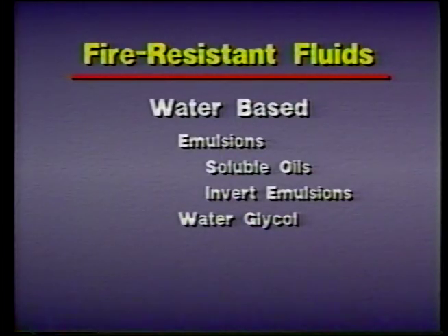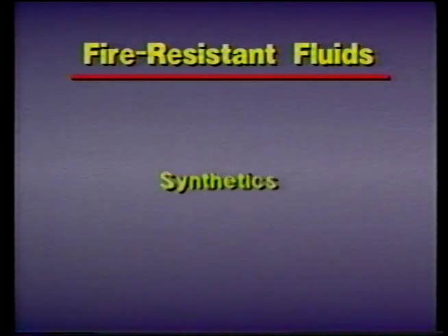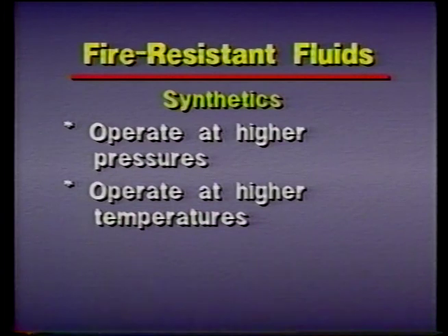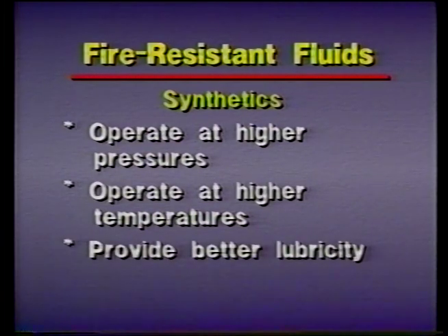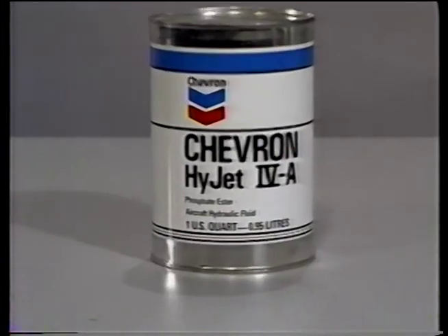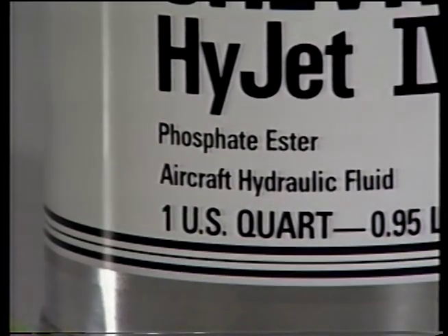The last category of fluids we need to discuss are the synthetic fluids. These man-made solutions operate at higher pressures and higher temperatures. They provide better lubricity, and in many instances are more fire-resistant than emulsions. They do, however, cost more than most water-based fluids. One common synthetic fluid is phosphate ester. It is often used in high-pressure systems where fire resistance is needed.